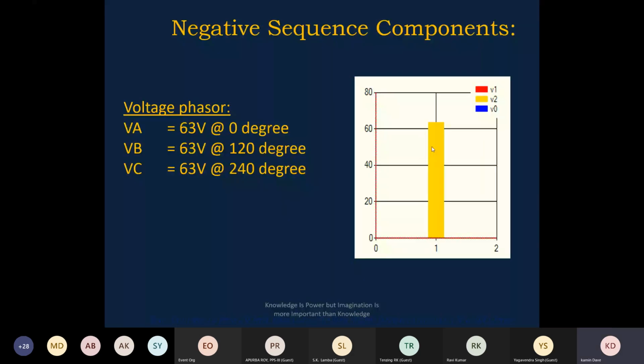When there is phase reversal, let us say 63 volt at 0 degree, 63 volt at 120 degree, 63 volt at 240 degree, it is 100% phase reversal. The negative sequence component becomes very high, 63 volt. So V1 plus V2 plus V0 is equal to V2 only, because V1 and V0 are equal to 0. So V2 is 63 volt. The negative sequence component is very high in this case.